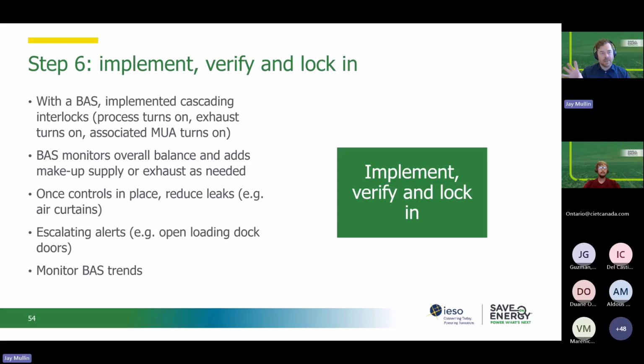So they have all these interlocks in place, but it's also like, okay, if the building is becoming negative pressure, then they'll turn on more makeup air supply to address that automatically. And then once those controls were in place and they had gotten the pressure balance under control, they started looking at reducing leaks, air curtains, improving the building envelope, that sort of stuff.